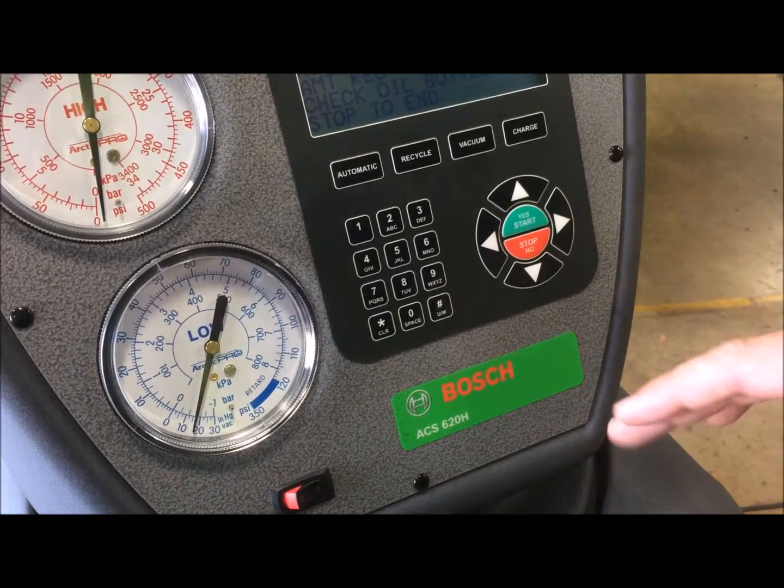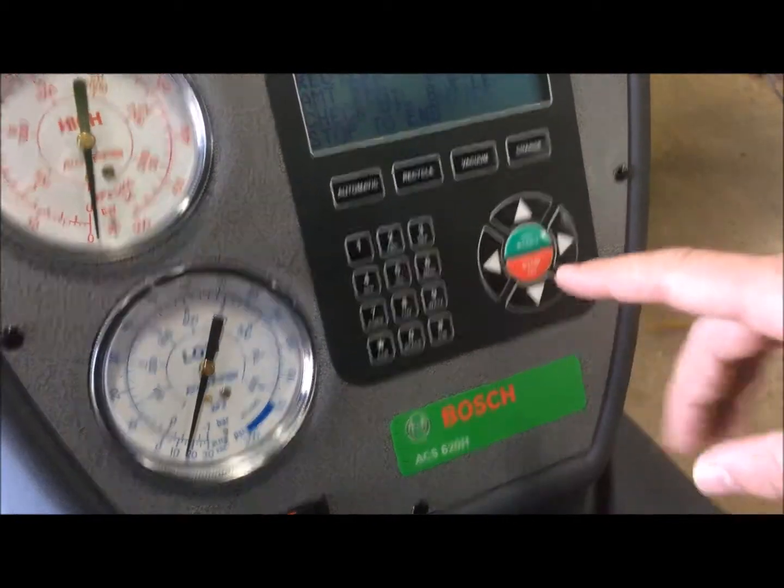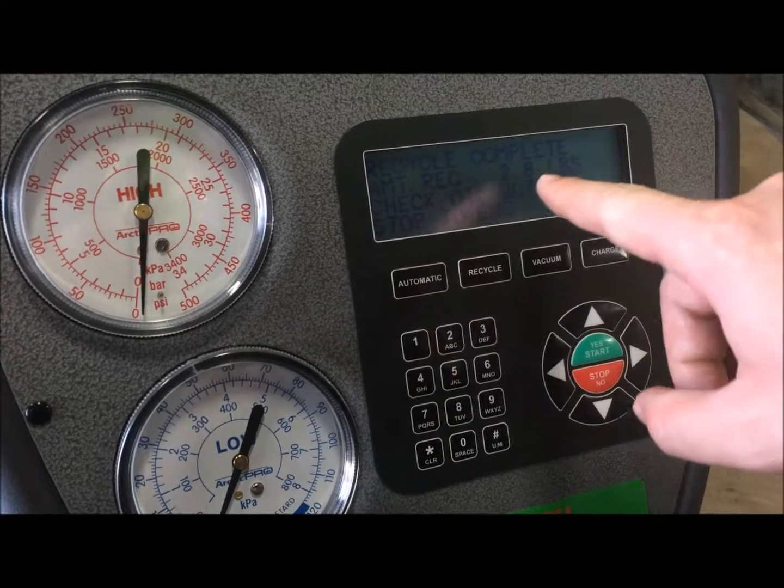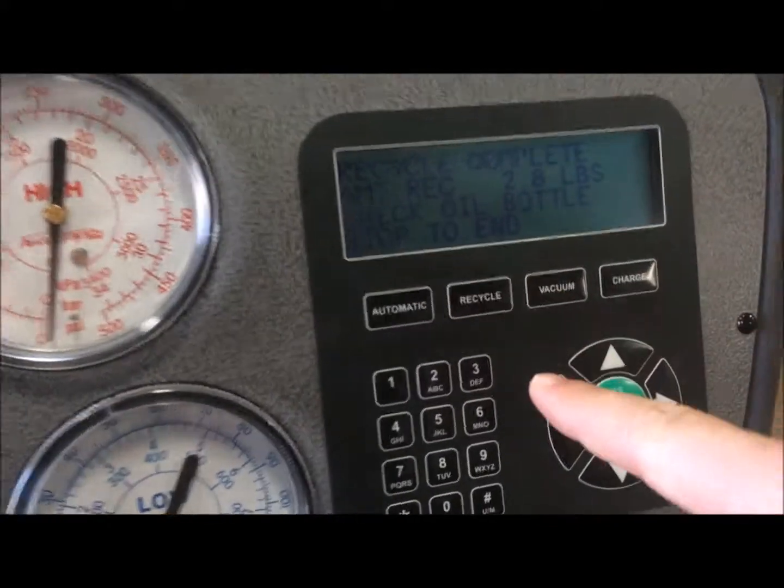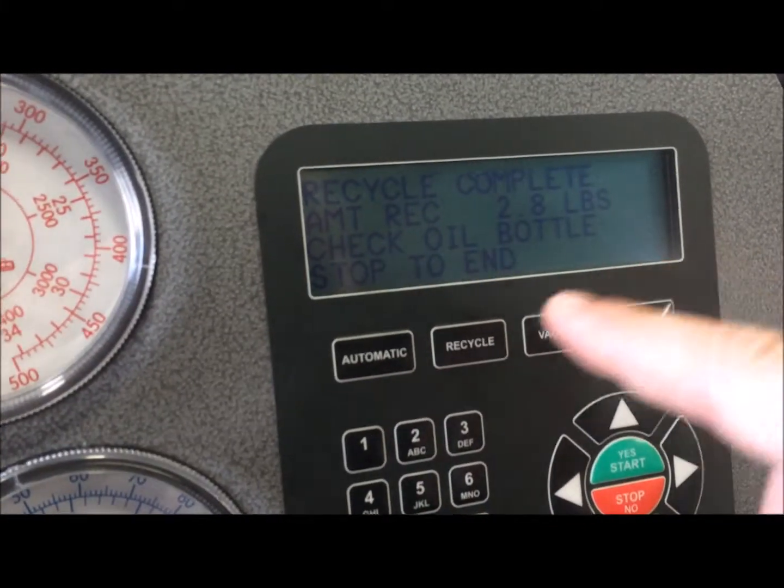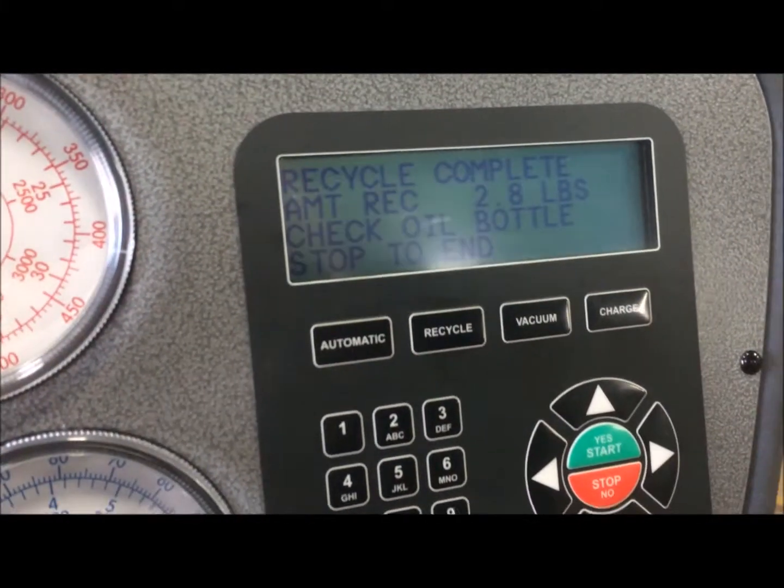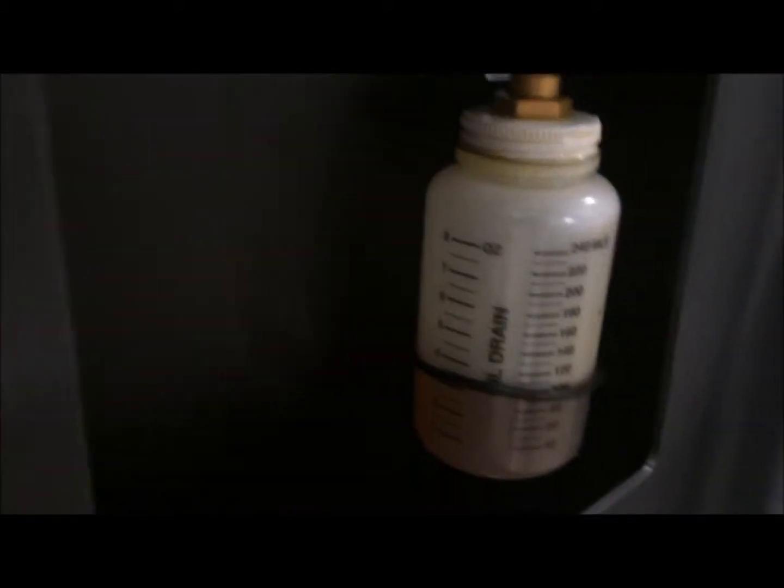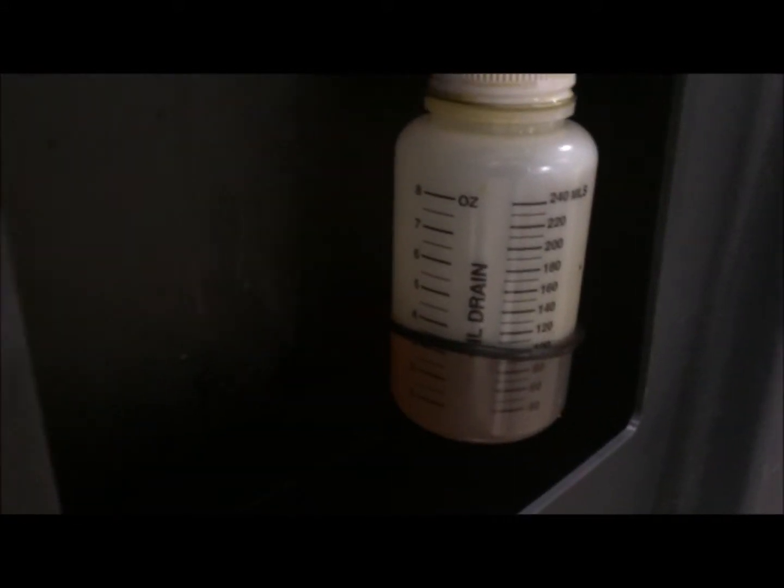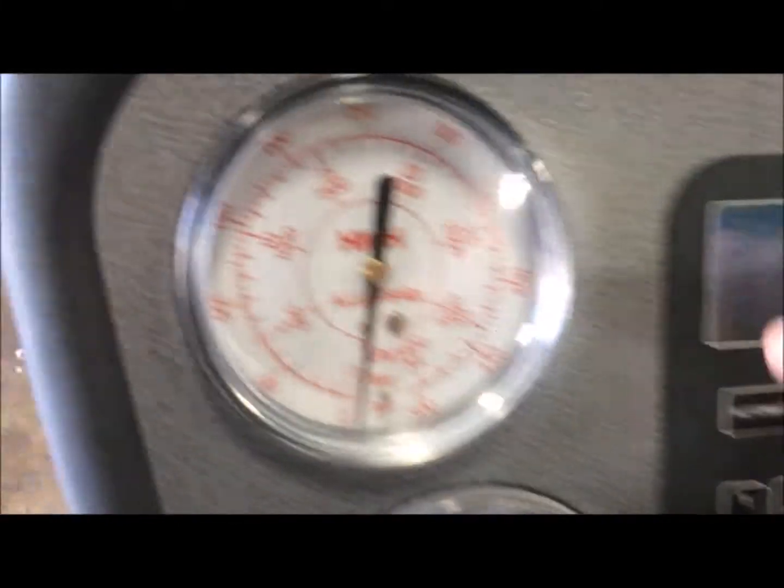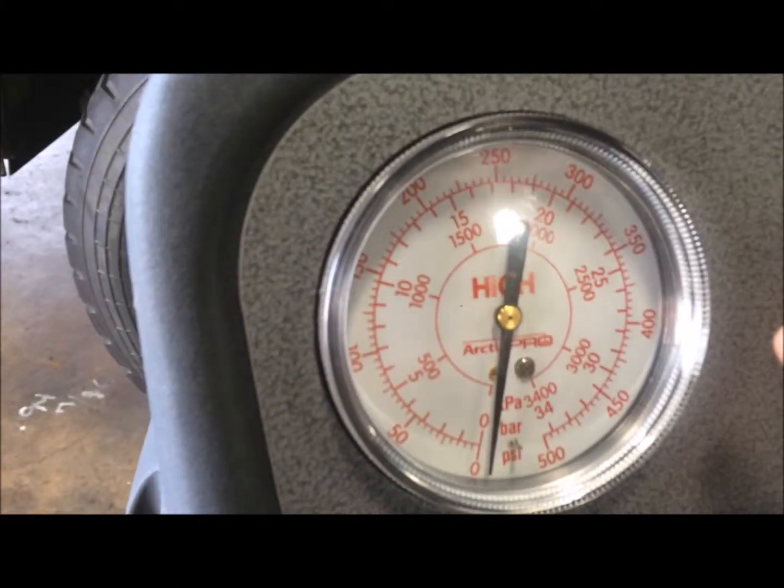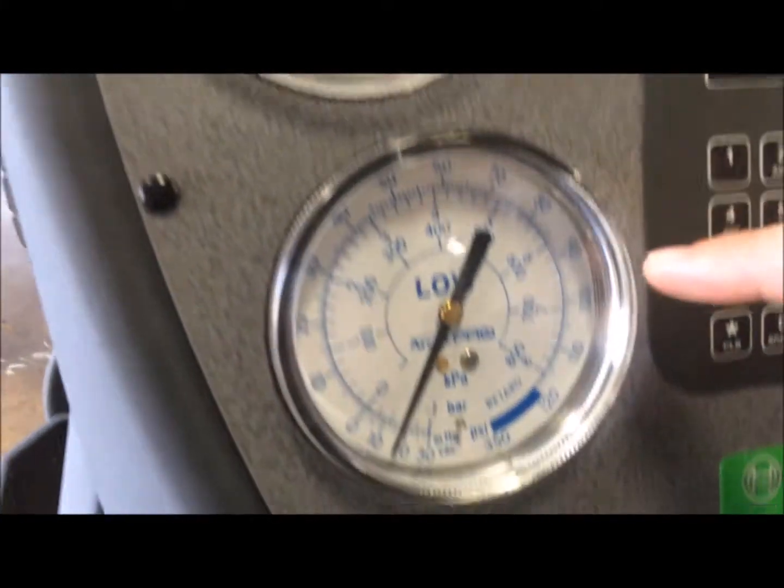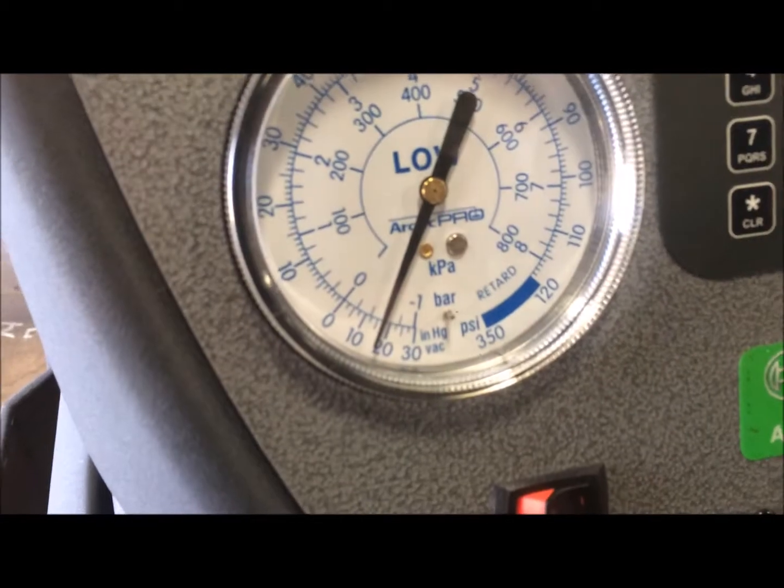Alright, the recover and recycle is complete. It shows the amount recovered, 2.8 pounds. It also says check the oil bottle and you can see the level to see if we recovered any oil. As you see, it looks like we didn't recover any oil. We're good. Also, you want to check and see that the system has no pressure in it on the high and low side.